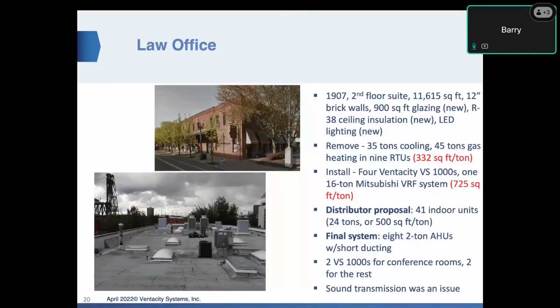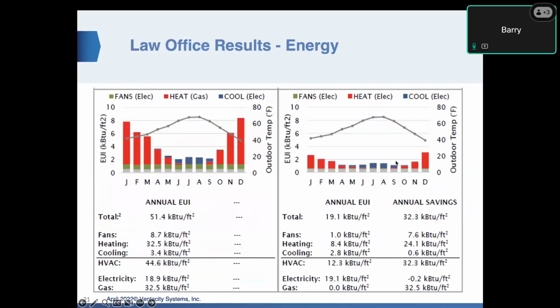This is a project we did. It's our first project in Portland, Oregon, where we took 45 tons of heating off the roof and replaced it with 16 tons of VRF. And this is the before and after. One of the biggest takeaways here, and the utilities like this: we took the electricity from 18.9 kBTUs per square foot to 19.1, and the gas went from 32 to 0. What that means is we didn't fuel switch. We didn't shift the load onto the grid, which is a lot of concern with utilities. They're going to get rid of the gas and put it on to the electric load. In most cases, we haven't done that at all.